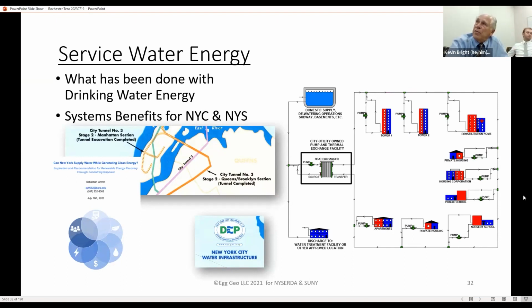Again, here on the right, we're showing this single pipe loop traveling around the neighborhood, and we can use that surface water to extract heat or reject heat too. One of the other interesting things: here we're just showing one source and sink to reject heat or get heat from. Realize that at some point we're going to overheat that water, or it's going to drop too low in temperature, so we could have multiple sources and sinks scattered around that neighborhood or city. We don't just have to have one. That's again the beauty of the single pipe technology; it doesn't really care where the sources are plugged into or where you're taking heat off or onto the loop.